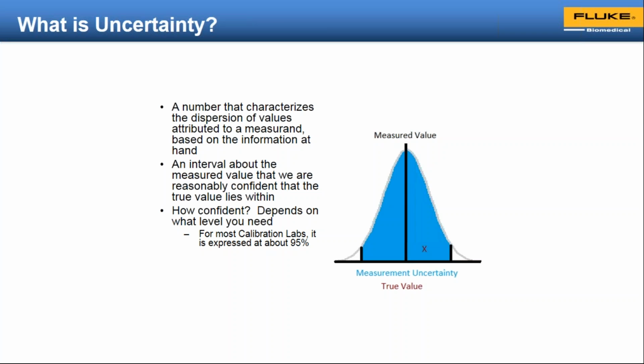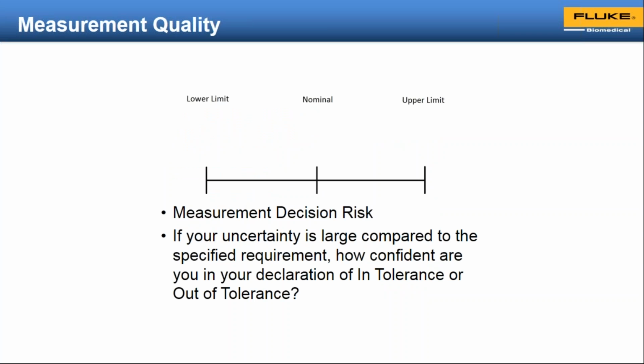And that is important to you because every measurement you make also has some uncertainties around it. You need to consider that and make sure you're making good decisions when you include those uncertainty bands we're talking about. We also want to measure quality and measurement decision risk. If our uncertainty is large compared to the specified requirement, how confident are you in your declaration of in tolerance or out of tolerance? So those are things that we need to consider.